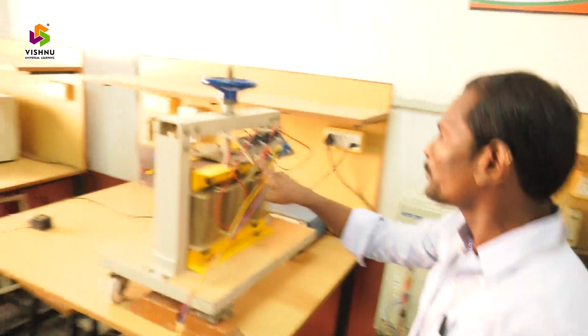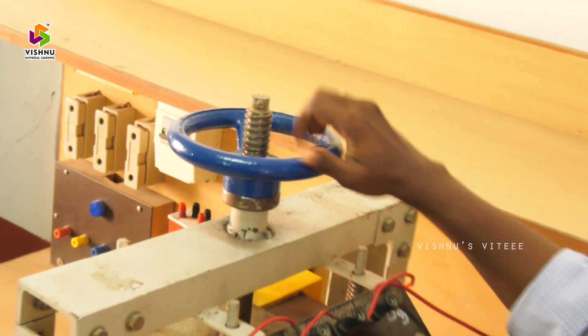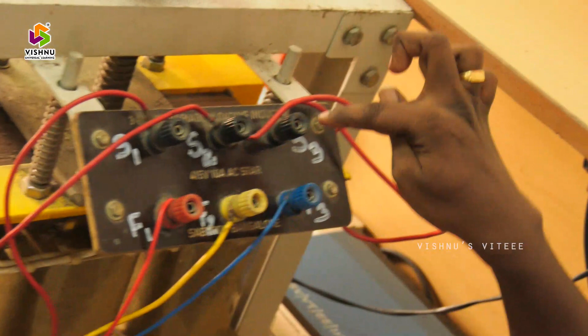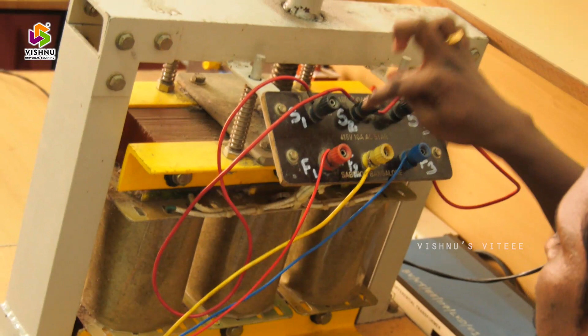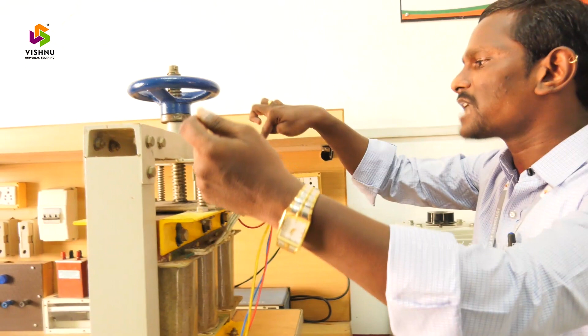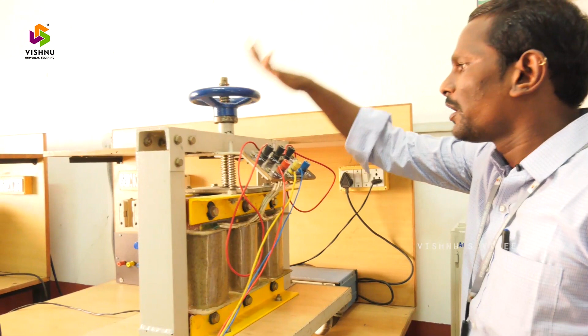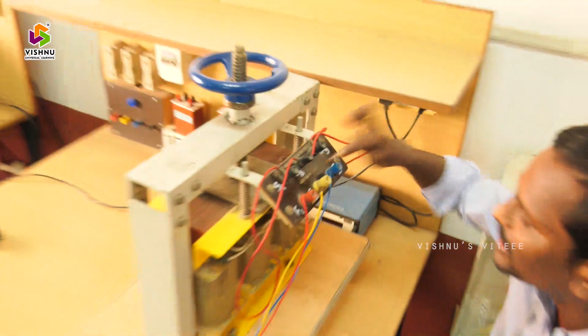Next, in our experiment, one more important equipment is the three-phase star connected variable inductive load. Here this wheel is used for variable load. Next, S1, S2, S3 are coil 1, coil 2, coil 3 starting terminals. F1, F2, F3 are the finishing terminals of these three coils. In star connection, these starting terminals are connected together. It means S1, S2 and S3 are connected together, or short circuited, for star connection. The rating of our load is 415 volts, 10 amperes. This is very important. Load current is 10 amperes.